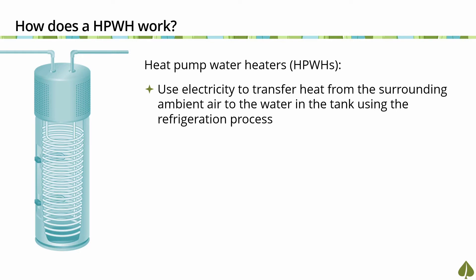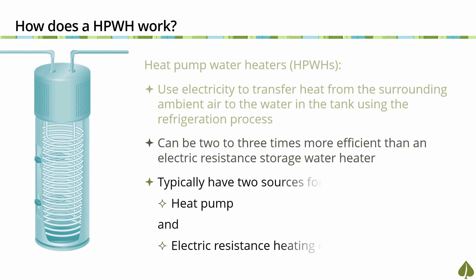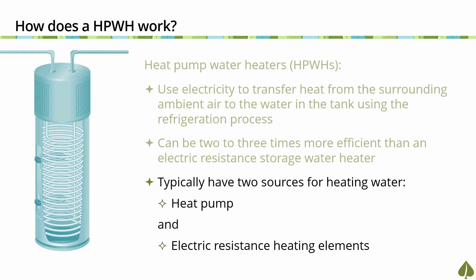This process for heating water can be two to three times more efficient than a similar electric resistance water heater. Typically, water heaters contain two sources for heating water: a heat pump and electric resistance heating elements. The heating source, which includes components such as a compressor, evaporator, and fan, are generally located at the top of the unit, while some units may have these components located separately outdoors with a tank located indoors.